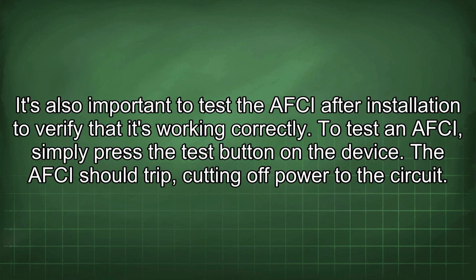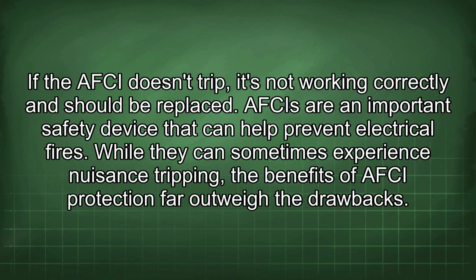It's also important to test the AFCI after installation to verify that it's working correctly. To test an AFCI, simply press the test button on the device. The AFCI should trip, cutting off power to the circuit. If the AFCI doesn't trip, it's not working correctly and should be replaced.